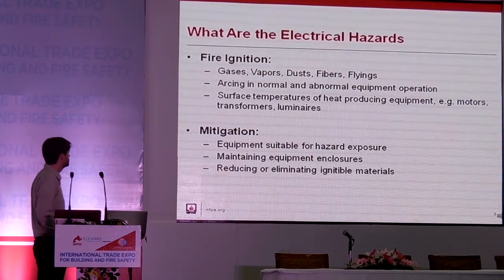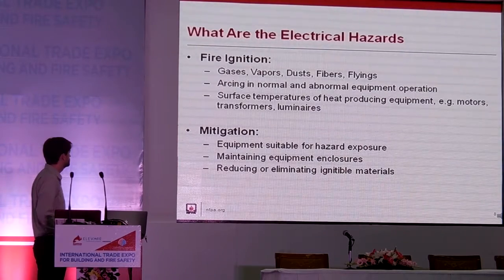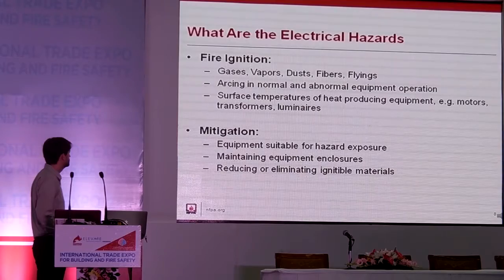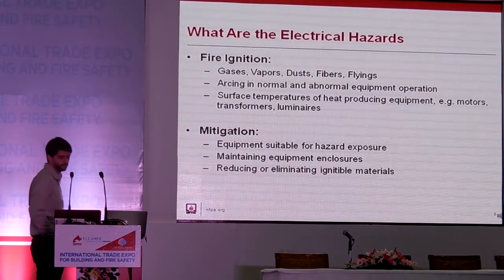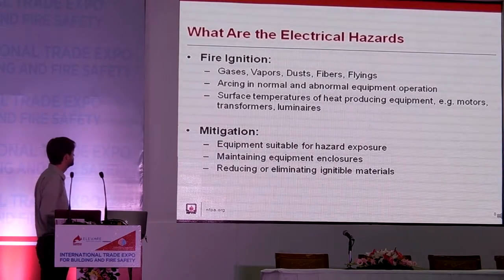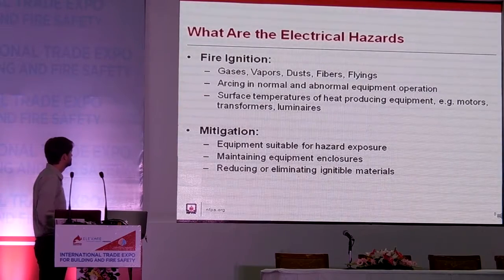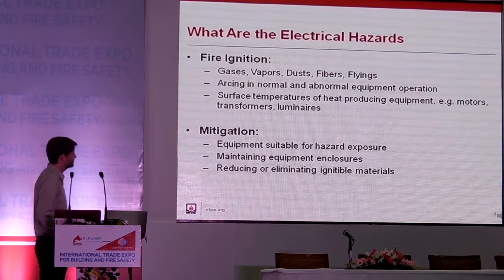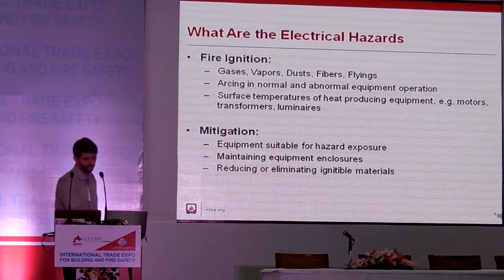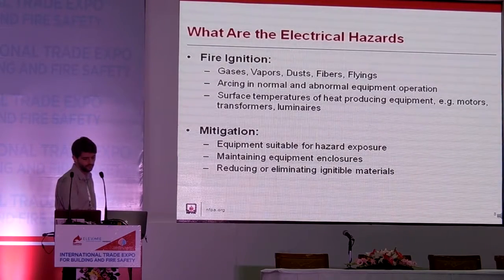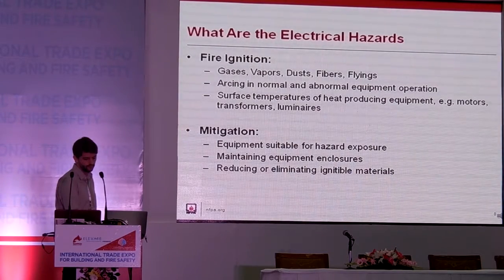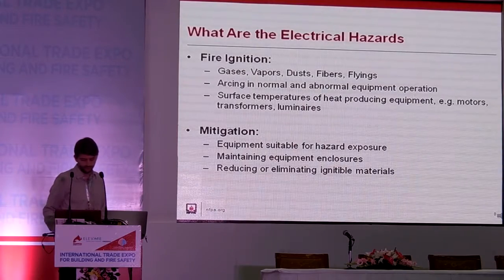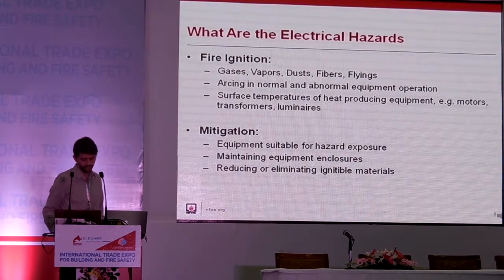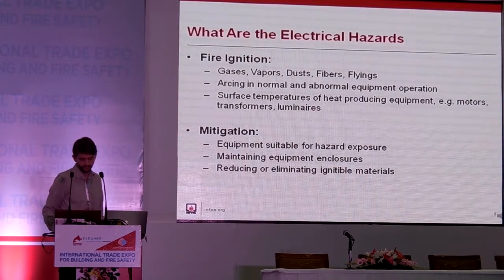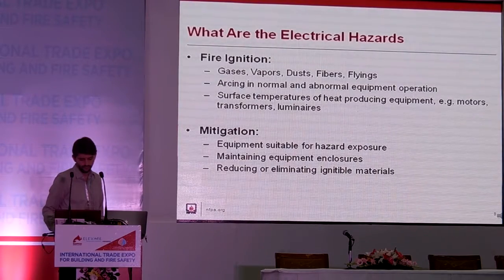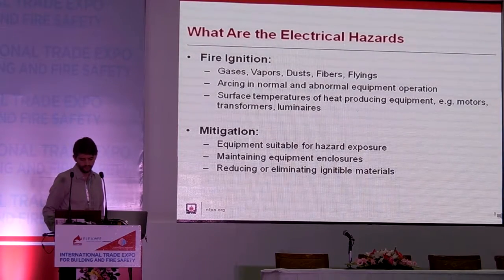Maintaining electrical equipment enclosures so that sparks cannot escape, or so that foreign material cannot make ingress into the enclosure, is essential. And then reducing or eliminating ignitable materials on the surfaces of electrical equipment, through dust removal systems or good housekeeping practices, is another way of mitigating the electrical fire ignition hazard.